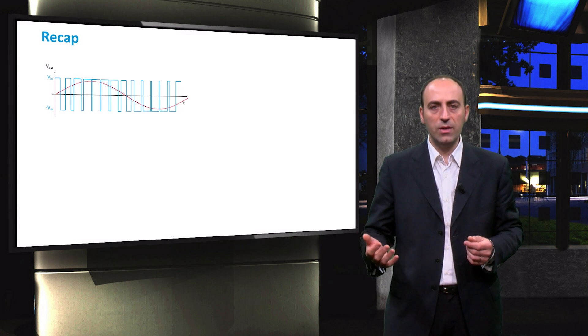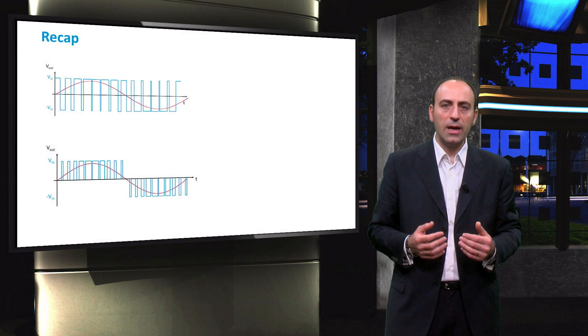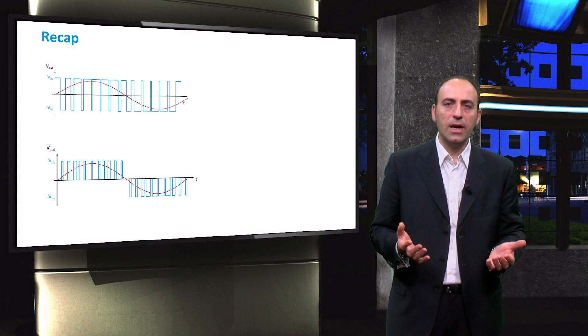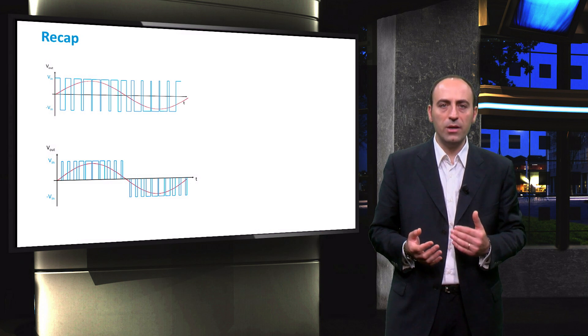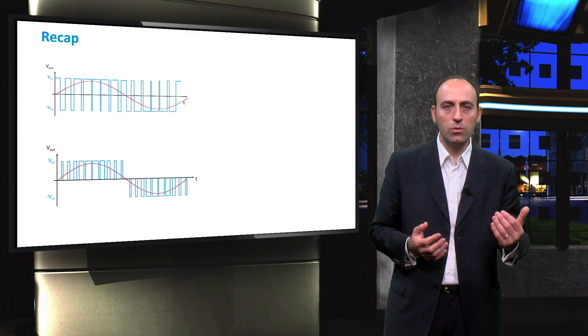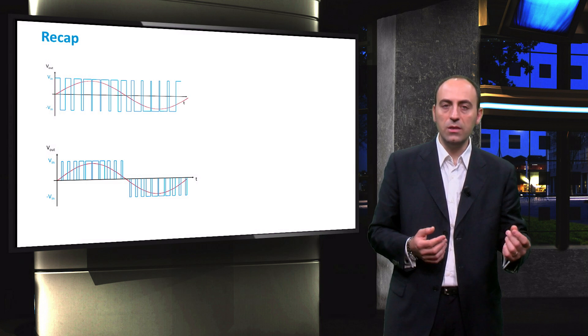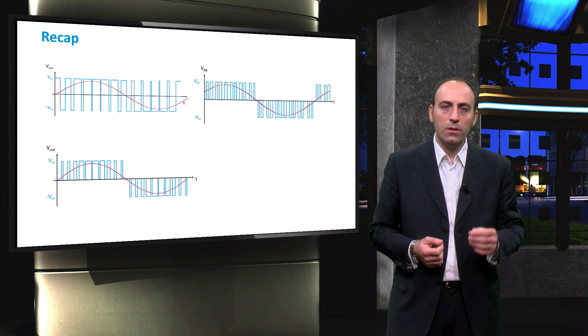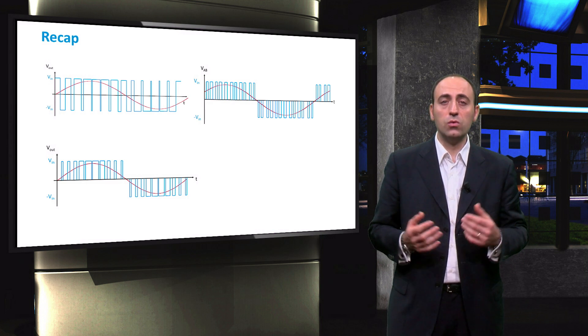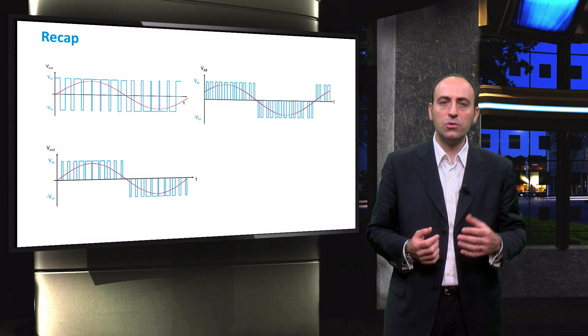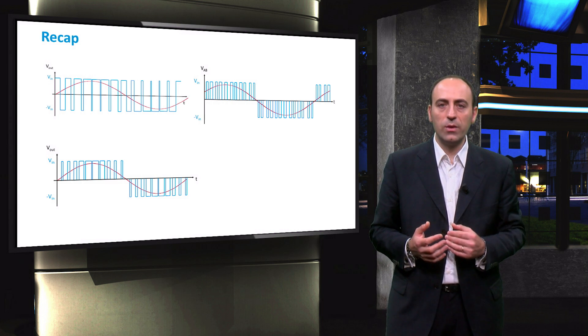The bipolar type acts simultaneously on the four switches of the inverter and gives a signal that goes from plus V input to minus V input. The unipolar type uses two input signals and draws in the first half period a signal that goes from V input to zero, and in the second half period a signal that goes from zero to minus V input.